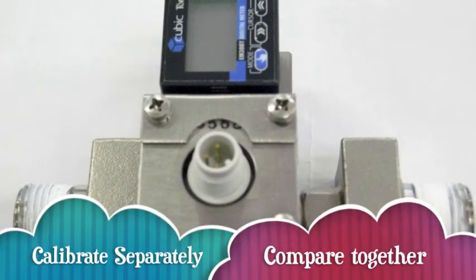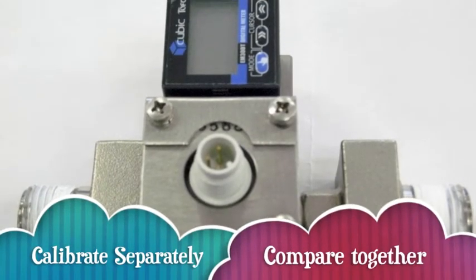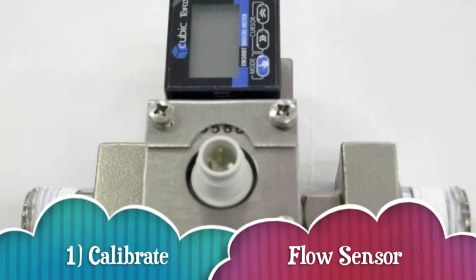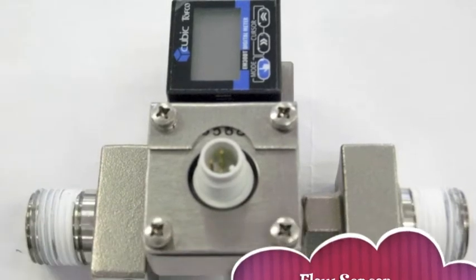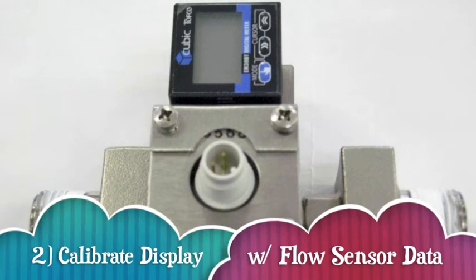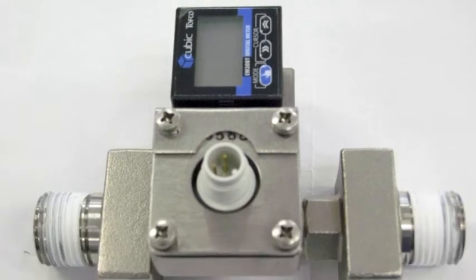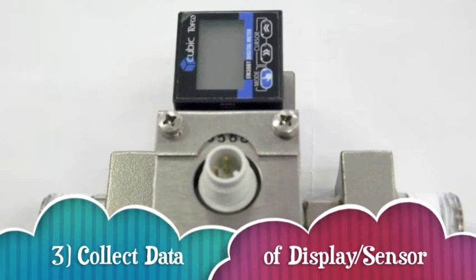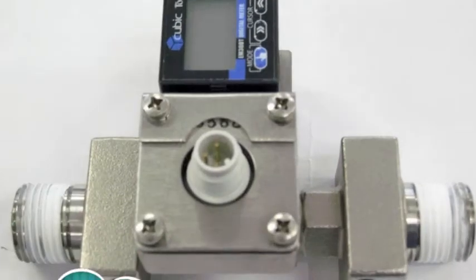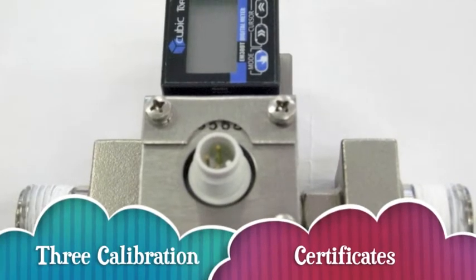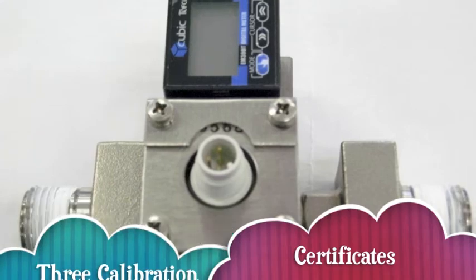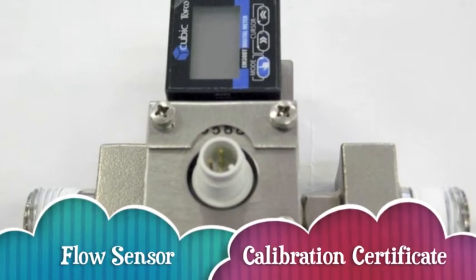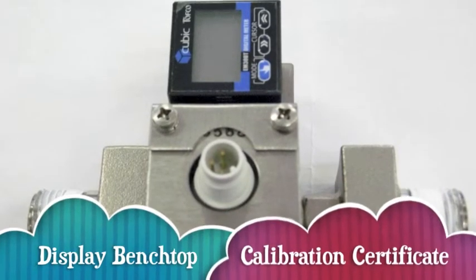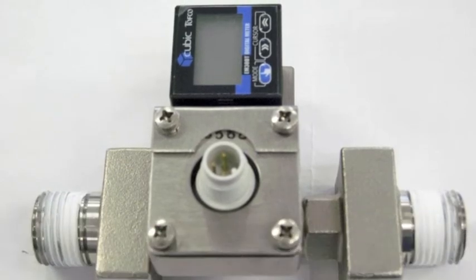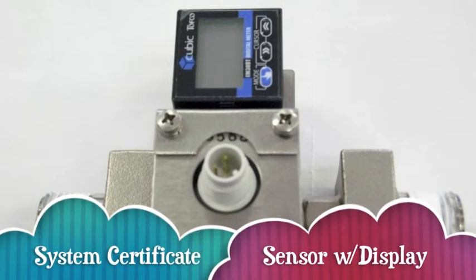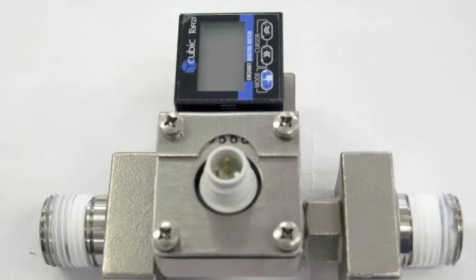System calibration for the V7000 and display would take three steps. First, calibrate the flow sensor, then take the data from the flow sensor and calibrate the display, then run the display and sensor together and collect data. For this system calibration, you will have three certificates: one for the flow sensor data, one for the display calibrated on a benchtop, and the third one for the verification of the sensor and display.